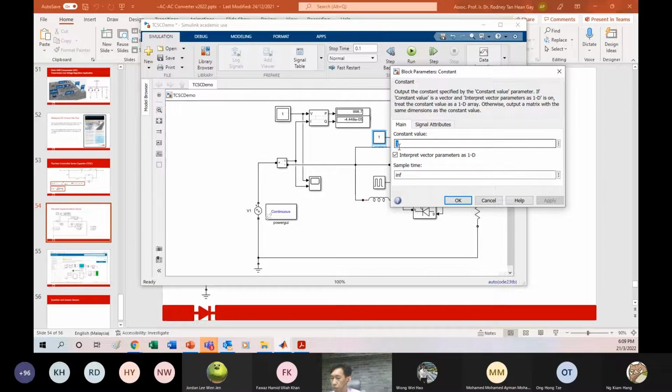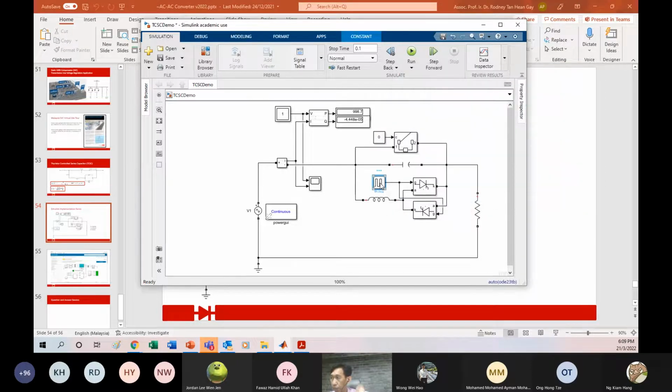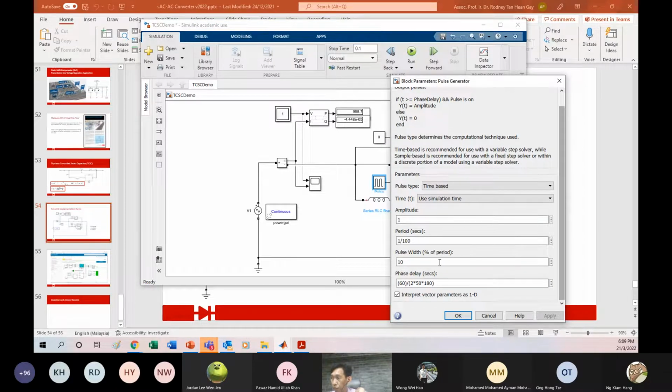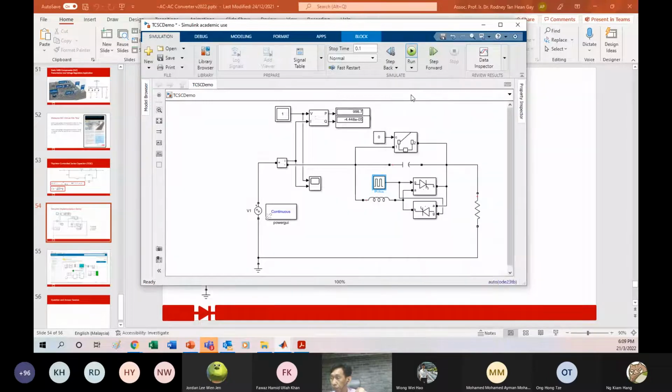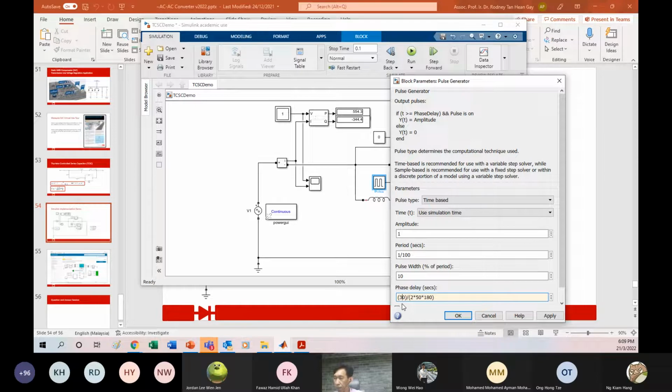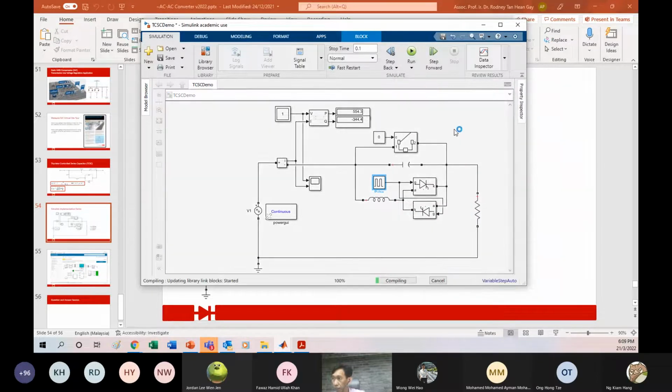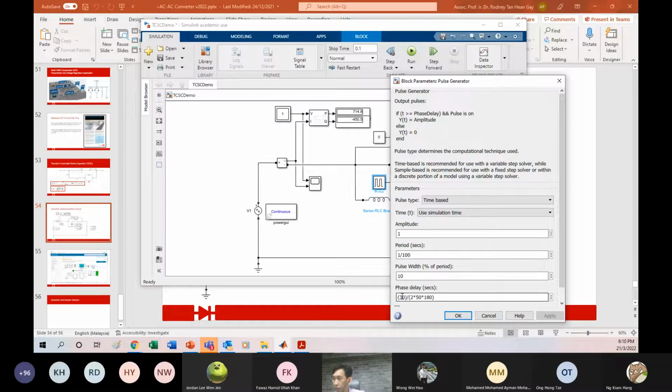So now I set this to zero. And then, again, I just play around with the firing angle. My firing angle is 60 degree. You can see that now my real power is only half, and I'm transmitting reactive power of negative 344. That means real power is going this side, reactive power is coming this side. So by changing this firing angle, let's say 30 degree, you can see that both also increase, because of the resultant of this parallel reactance. And I can put like 10 degree.